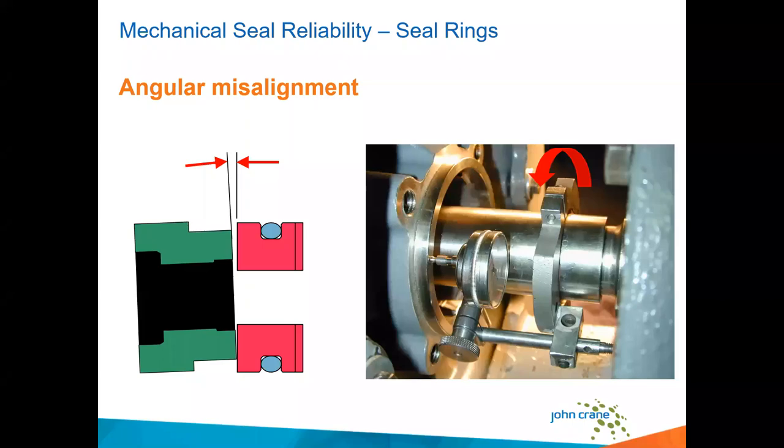If we make that seal head stationary and it's not rotating with the shaft, it's now able to essentially flex once, because that's typically going to be our spring-loaded member, that seal head. If that's stationary, that'll flex maybe one time with the shaft rotation and then run in that position. So if we suspect angular misalignment, we can look at orientation of the seal and maybe go from a rotating seal head to a stationary seal head to help offset some of those issues.